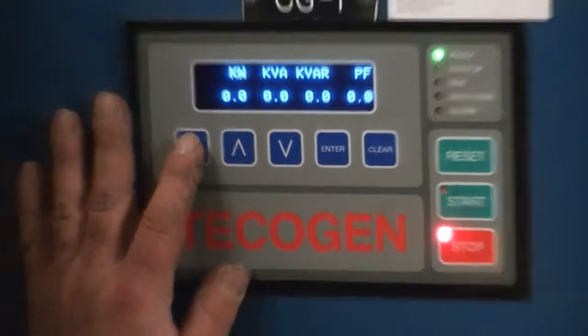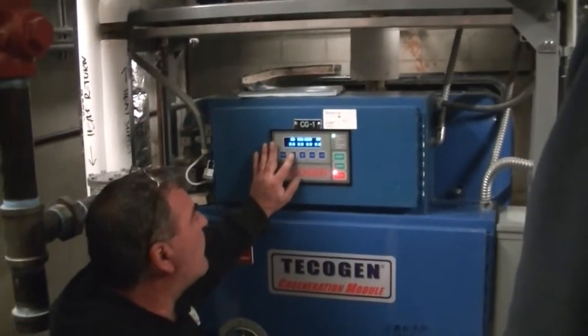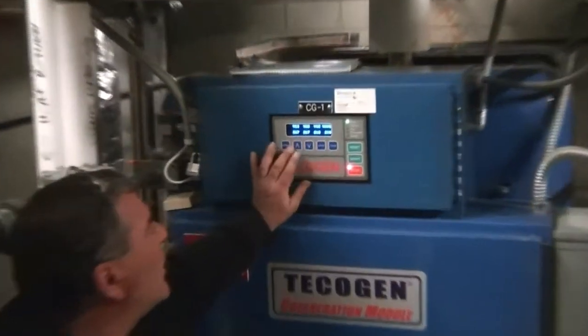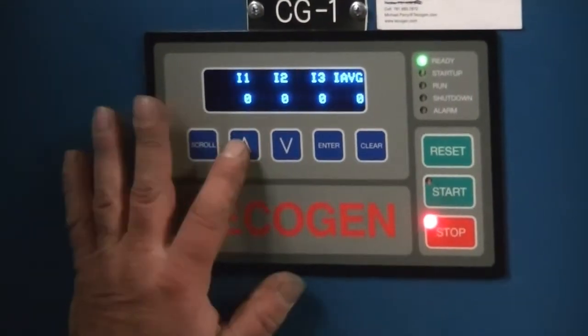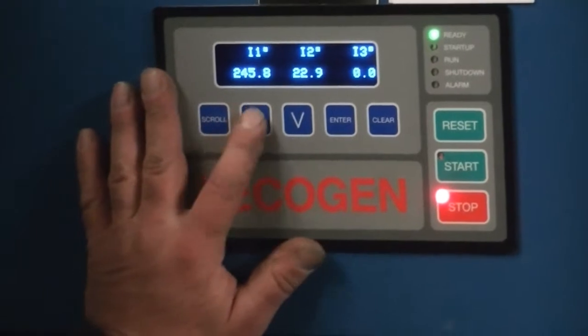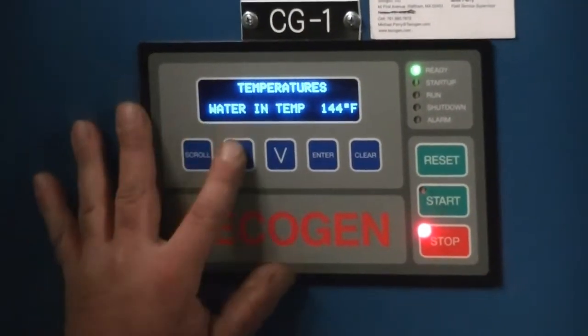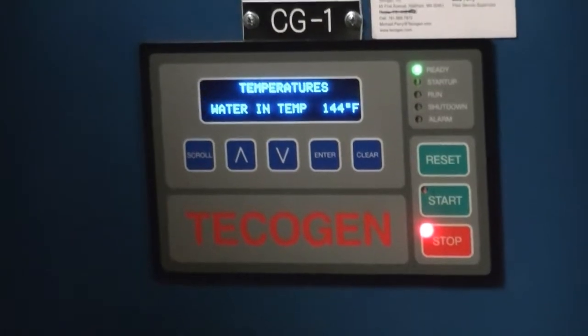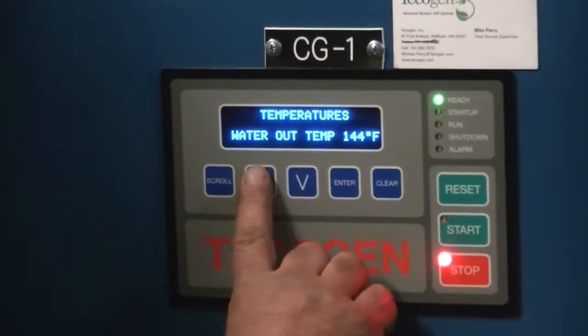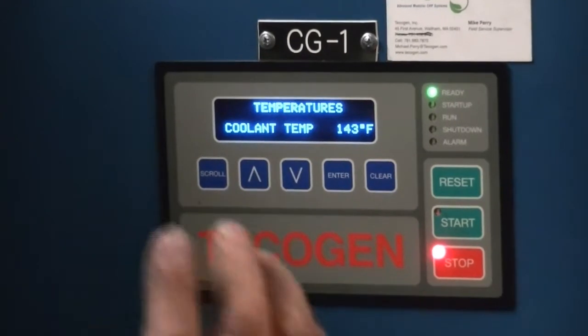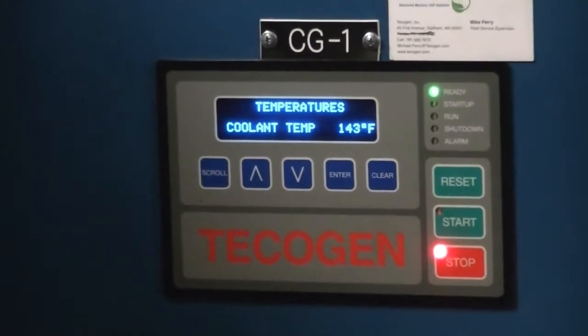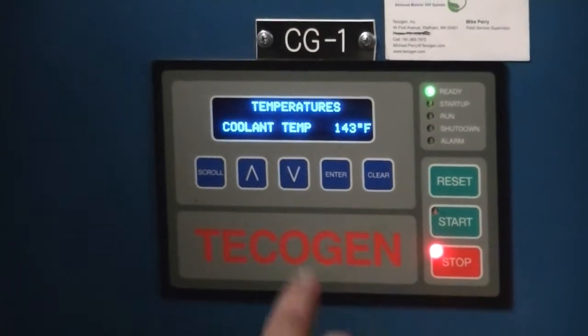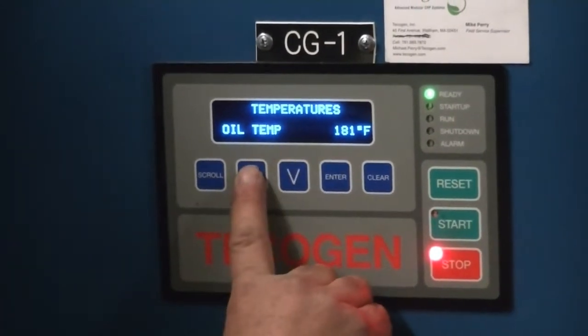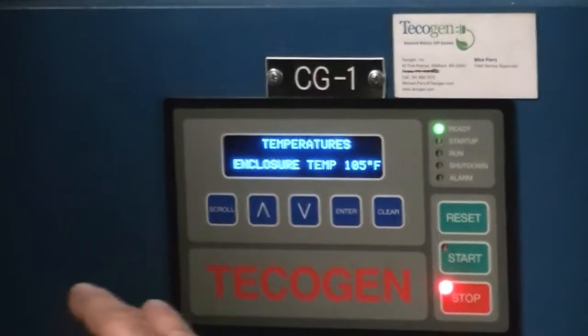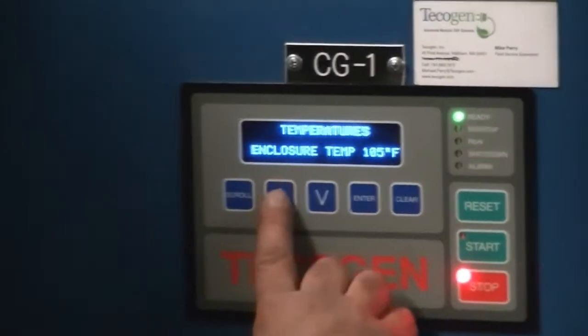No, that's a fan. And then you have all your information for your voltages. That's the voltage on each leg, the average, the current, the frequency. We have temperatures from the water in to the machine, the water out of the machine. Coolant temperature is the temperature inside the engine. Like on your car, you have the oil temperature. The enclosure temperature is the temperature inside the enclosure when the covers are all on.